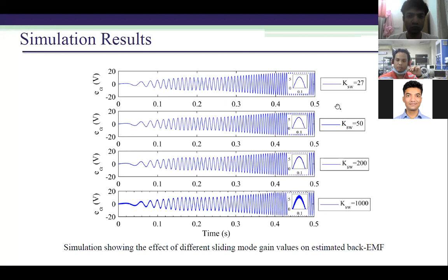And how to choose the feed forward path scaling factor in the structure? As I mentioned earlier, there was a scaling factor which I was using for converting the reference speed into the feed forward path. So how to choose that gain value? We conducted some simulation studies. We had chosen two sets of feed forward gains. One is dynamic gains, which vary along with the reference speed. Another one is constant frequency gains, a feed forward value which is based on the fundamental frequency.